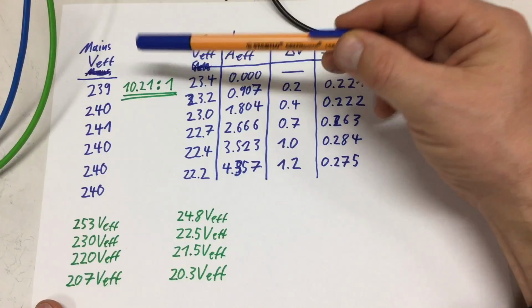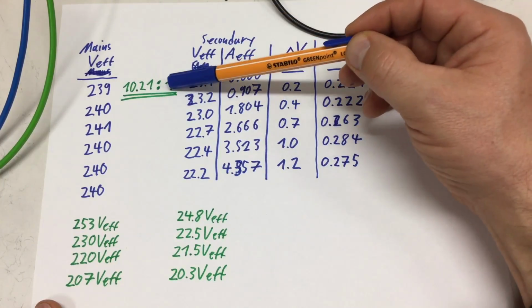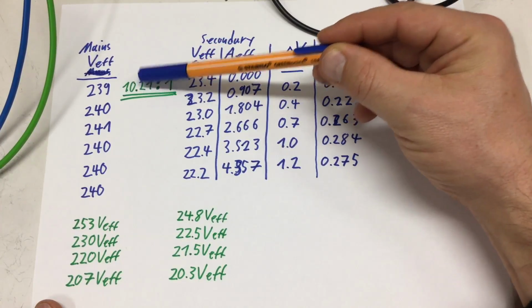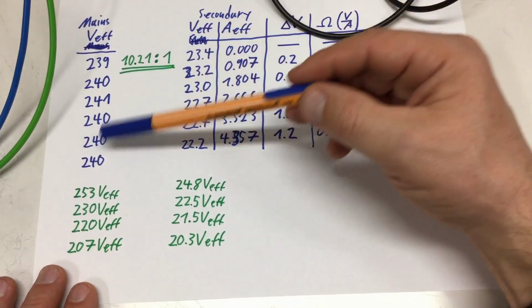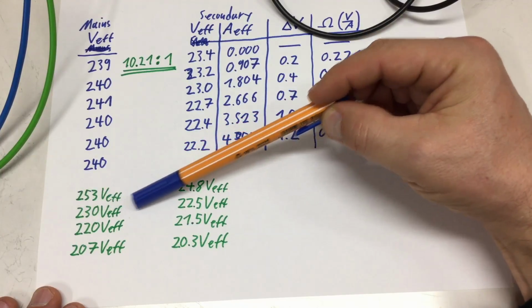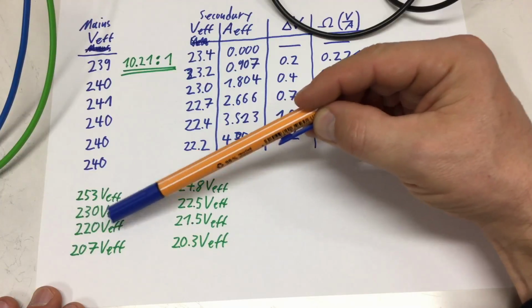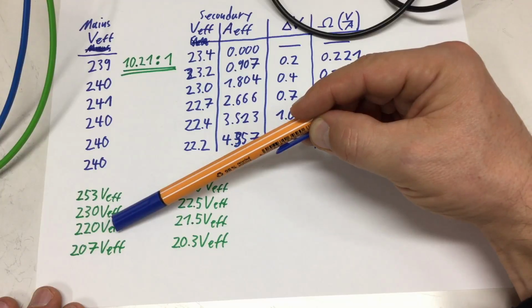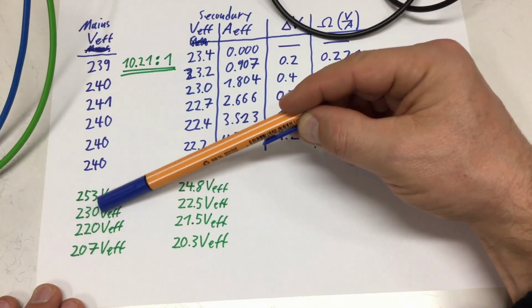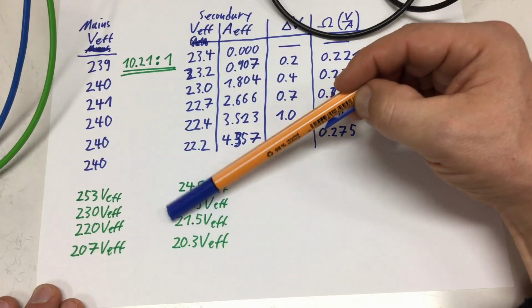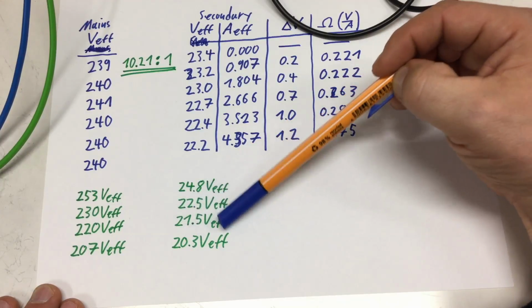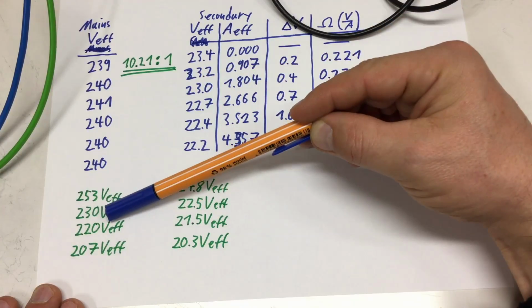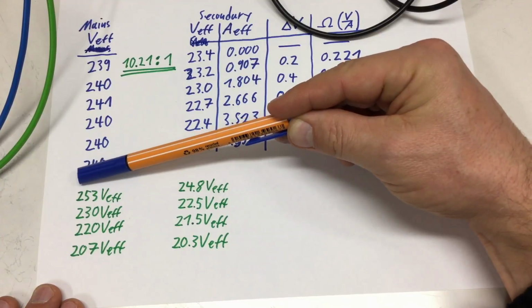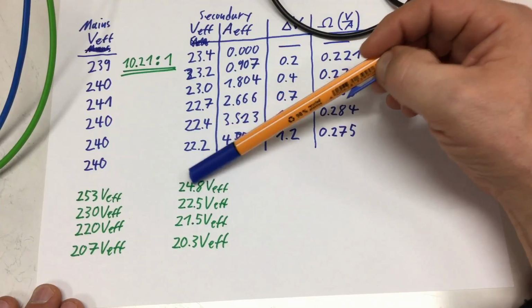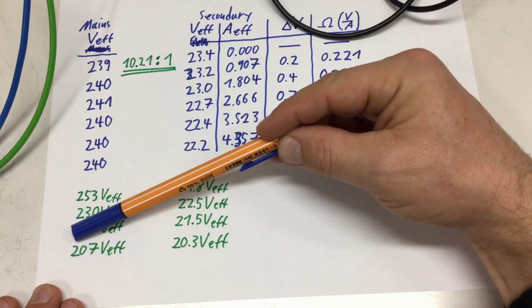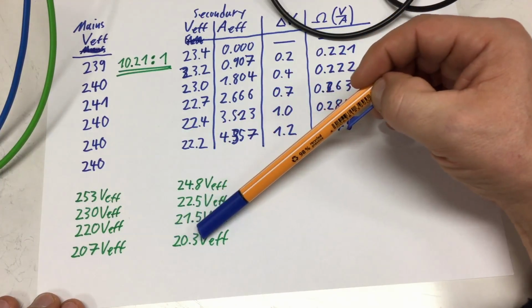And then we get the transformation the transformer is actually doing, and the output voltage is 1 over 10.21 of the input voltage, and this gives us at nominal voltage of 230 volts, 22.5 volts. At 220 volts, which was the old nominal voltage in Germany before Europe came - we had 220 volts, not 230 volts - it would have been, and that was the design point for the power supply, 21.5 volts. And since we have 230 volts plus minus 10%, it can go up to 253 volts, giving us 24.8, or as low as 207 volts, giving us 20.3 volts.